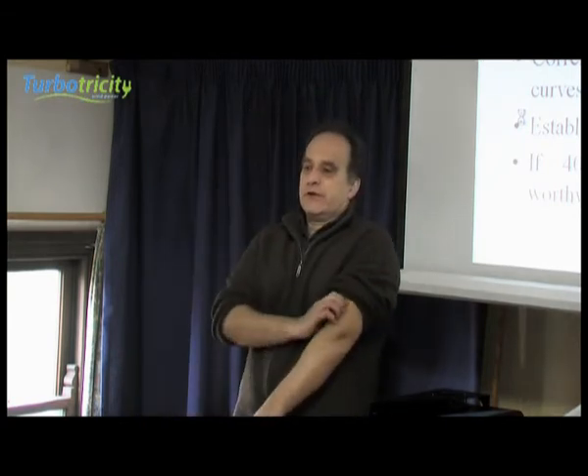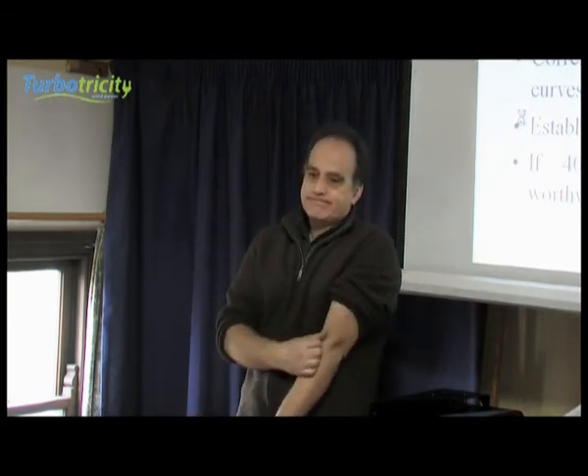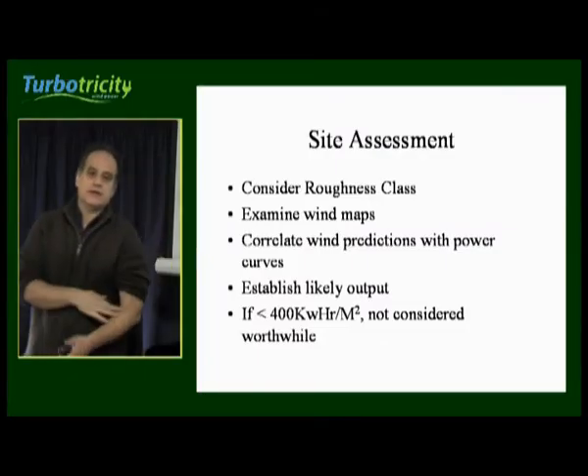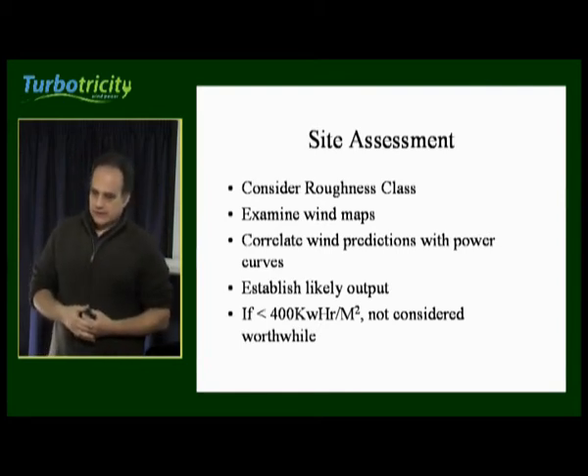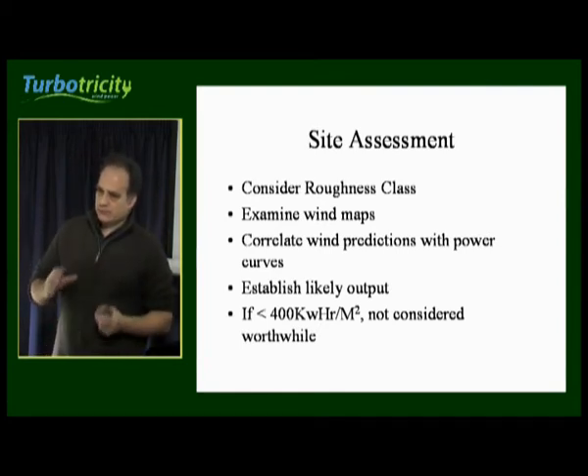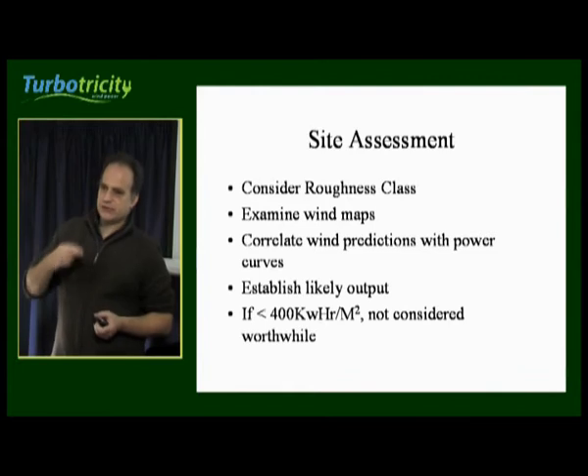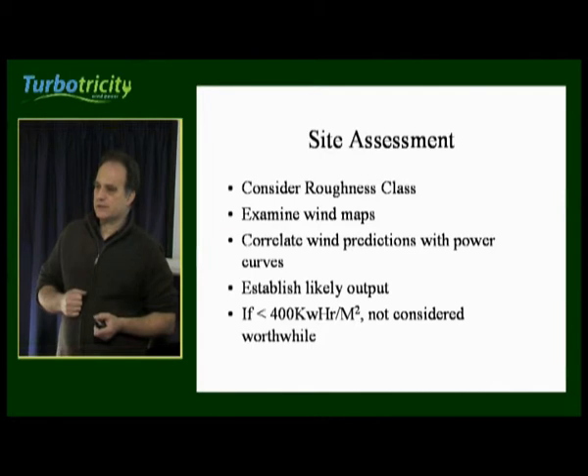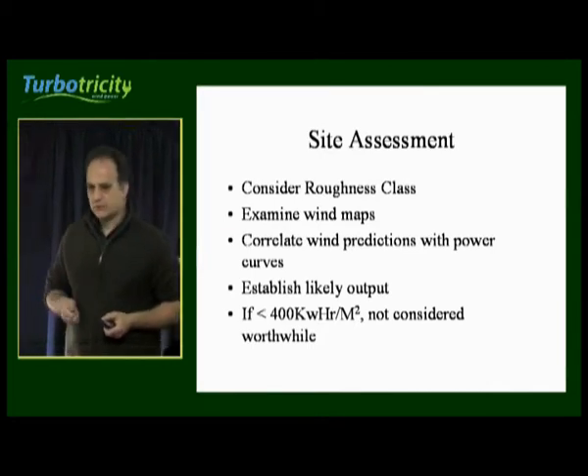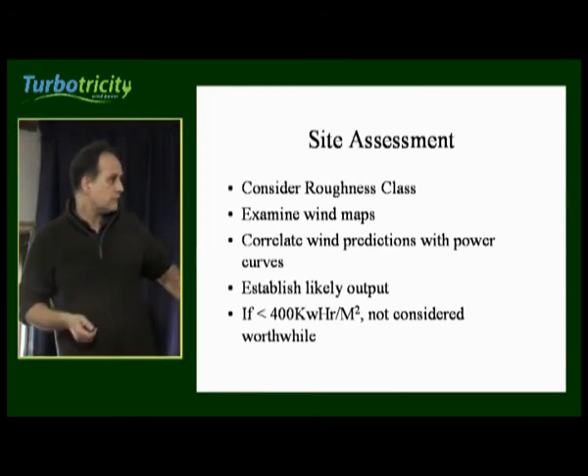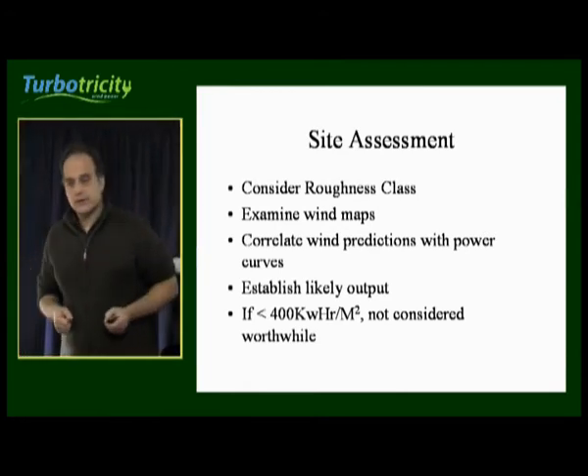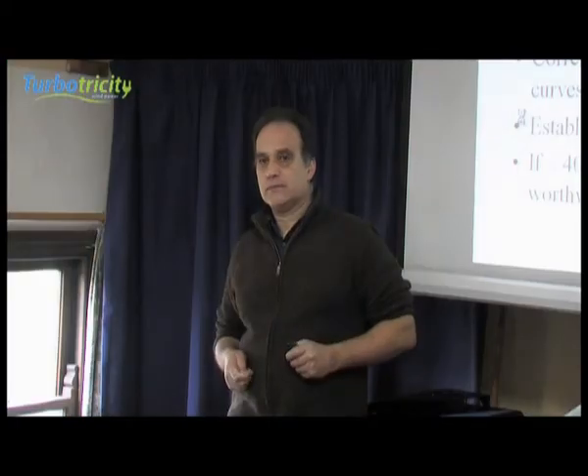We come on to the DESK method for assessing your site. First of all, you have to consider what the roughness class of your land is. You then examine wind maps and find out what the mean wind speed is in your area. You can correlate the wind predictions for your site with the power curves for your turbine, and then establish the likely output. If the net result is an output below about 400 kilowatt hours per square metre per year, the site is considered not worthwhile.